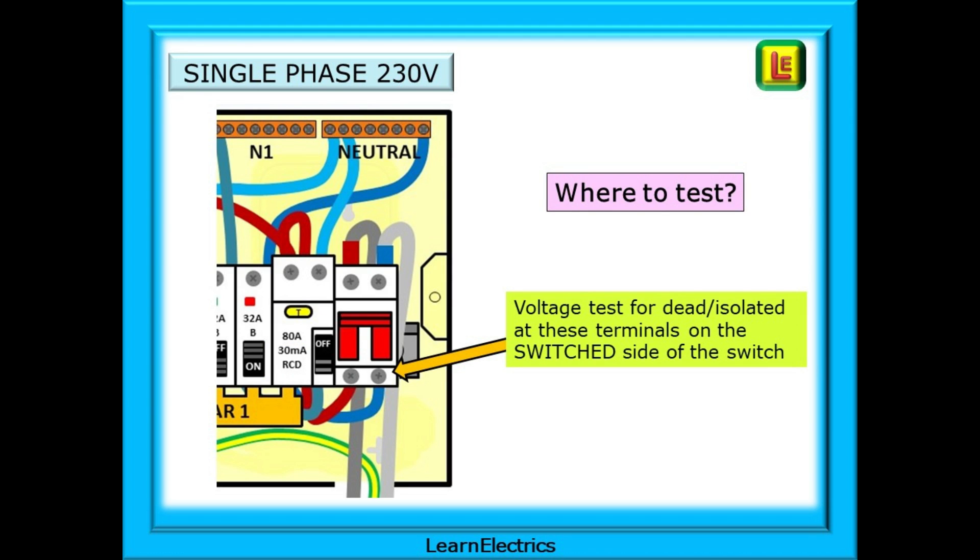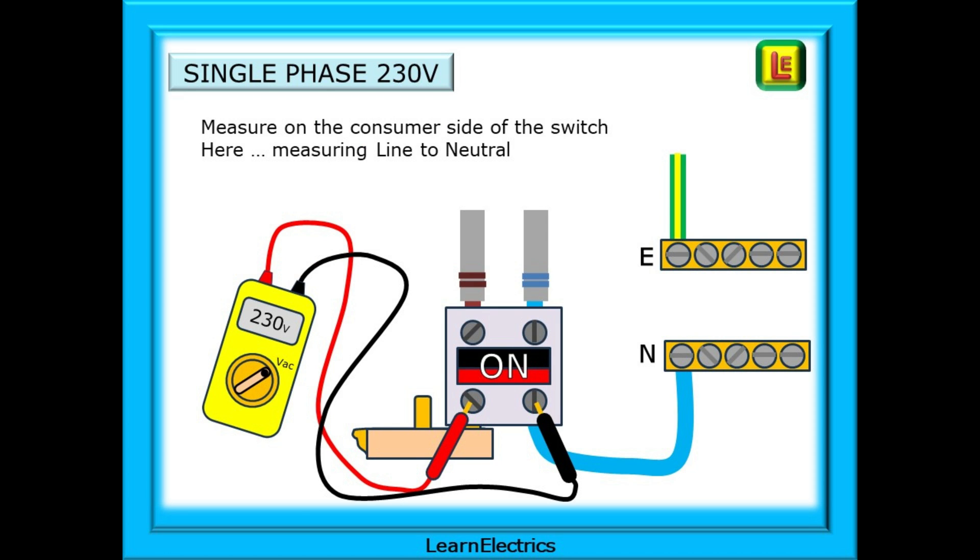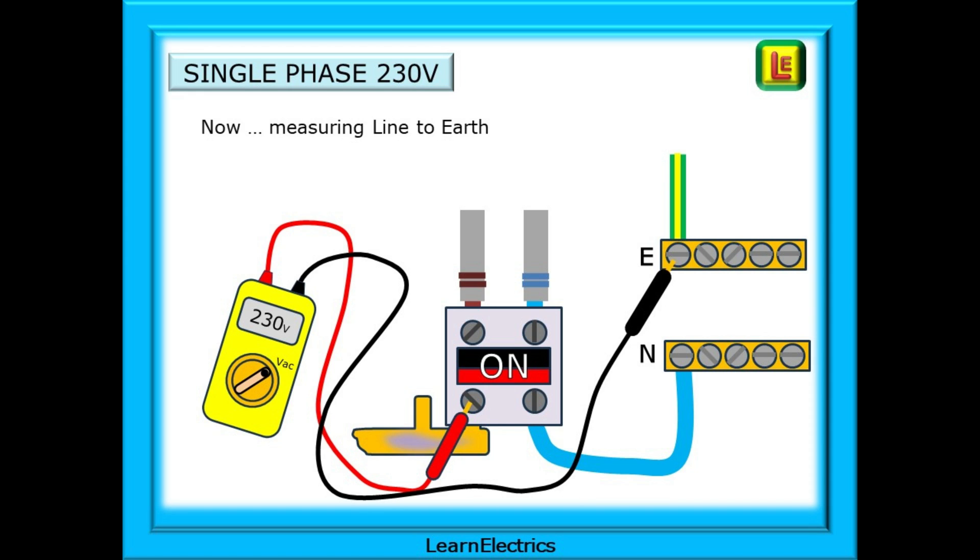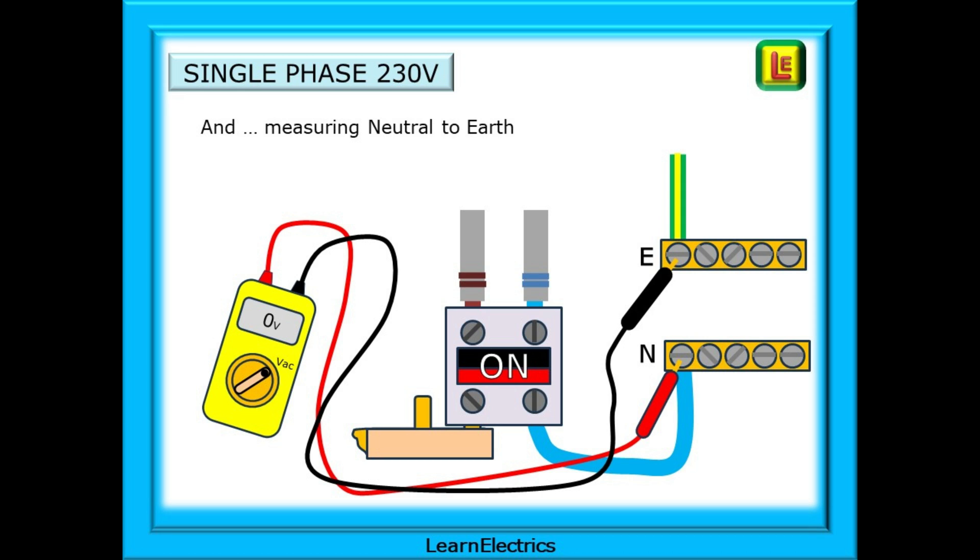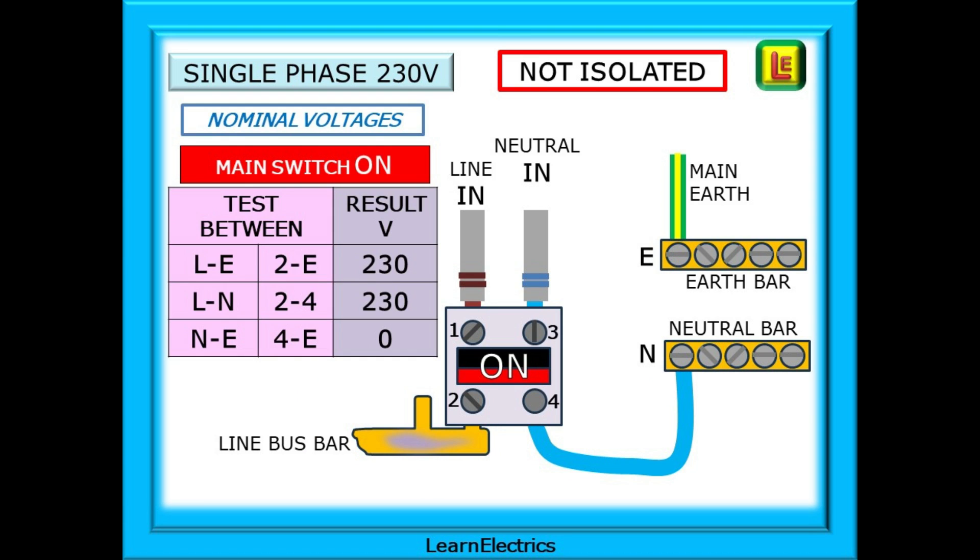Where are we testing? We will voltage test for dead or isolated at the bottom terminals, those on the switched side of the switch. Even though we might be testing for dead, testing for no voltage, we should treat these as live tests and take suitable precautions for the safety of ourselves and others. Here, you might be measuring the line to neutral, and you will be close to potentially live parts. Is the bus bar covered with a plastic sleeve? Are there exposed connections where breakers are missing? And so on. Measuring line to earth still requires you to be close to the bus bar, which may or may not be covered, and testing neutral to earth is the last of the three tests on the single-phase consumer unit.